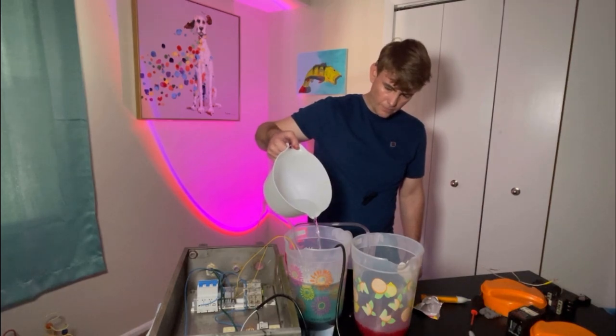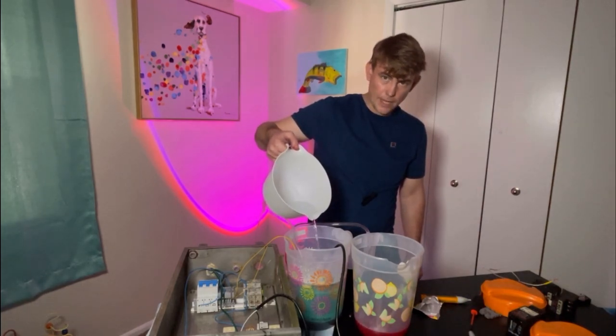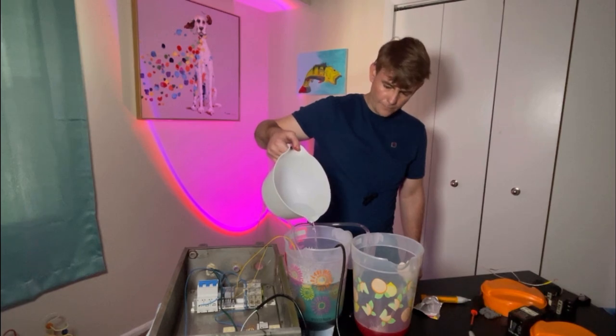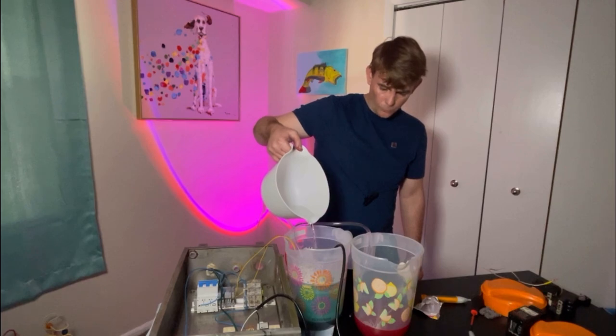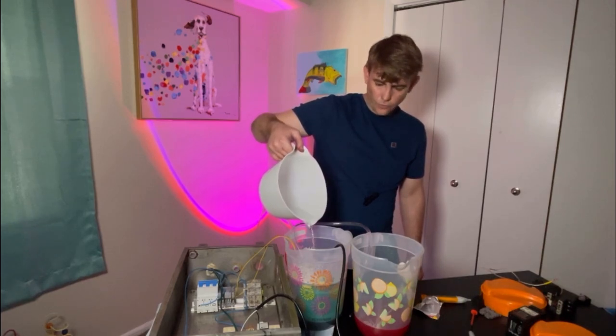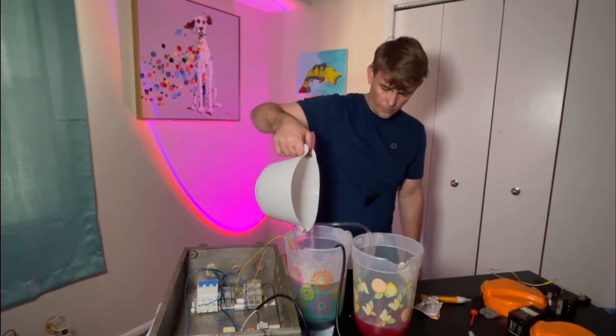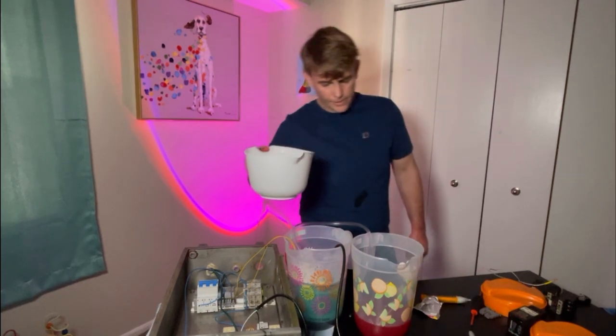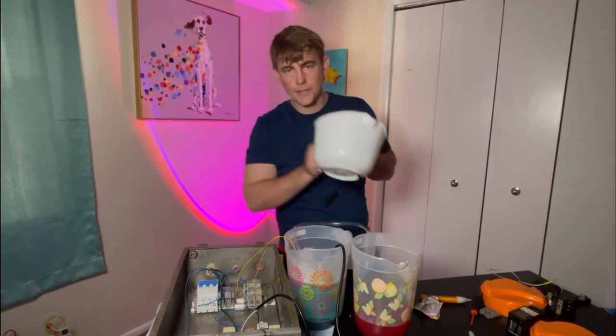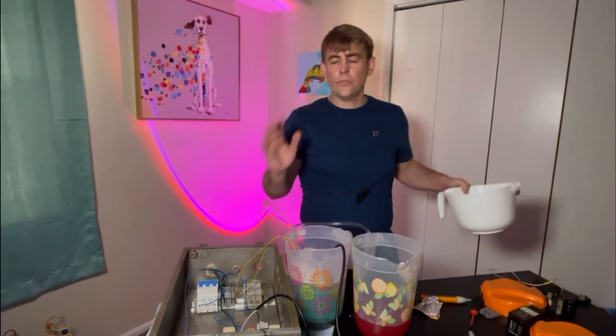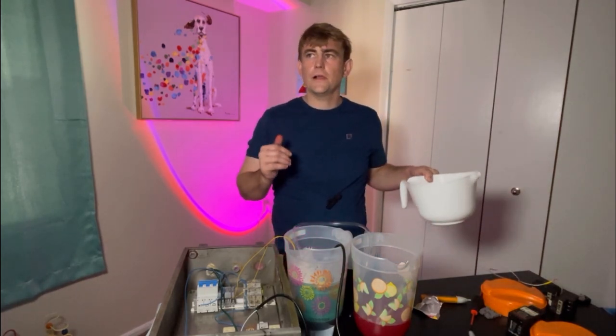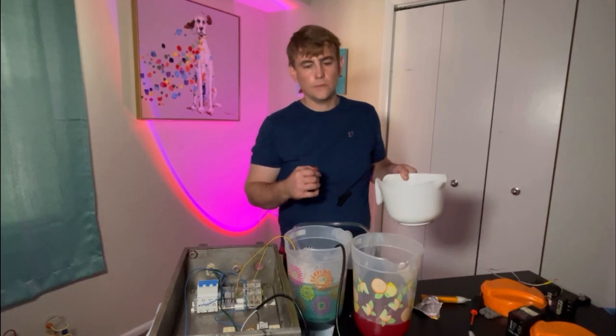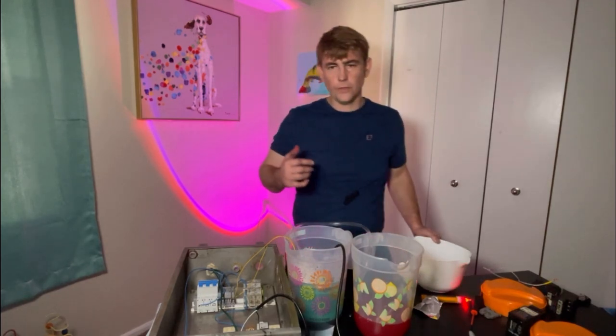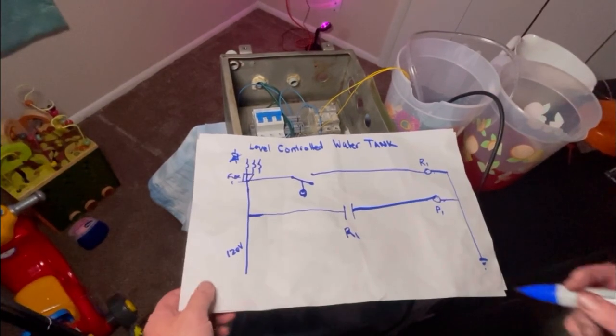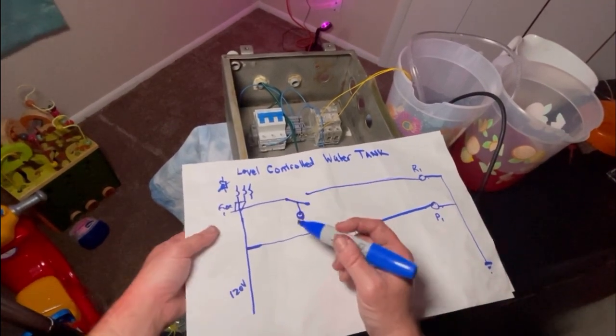The reason being is that we're just using a single float switch to control our process. It's a momentary float switch. You can see it pumping up and stopping, and then again it's going to pump for a second and stop. No bueno. What are we going to do to fix the problem? I'm sure I'm explaining it better right now. I look like I'm really into it, but that's okay. We're going to make do with what we got. So what we're going to do is we're going to seal in relay 1 with itself.